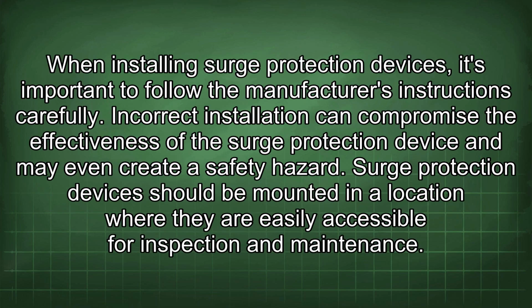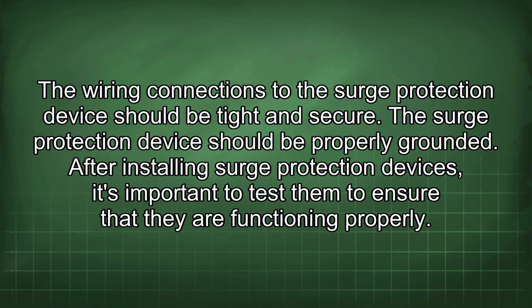When installing surge protection devices, it's important to follow the manufacturer's instructions carefully. Incorrect installation can compromise the effectiveness of the surge protection device and may even create a safety hazard. Surge protection devices should be mounted in a location where they are easily accessible for inspection and maintenance. The wiring connections to the surge protection device should be tight and secure. The surge protection device should be properly grounded.